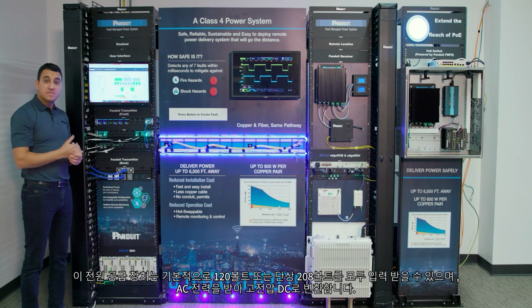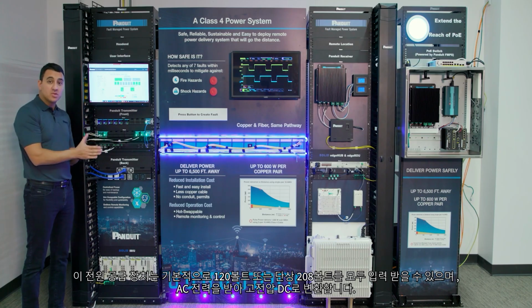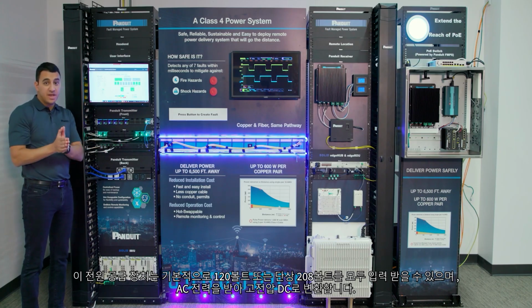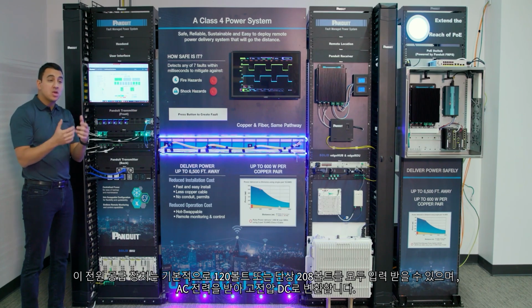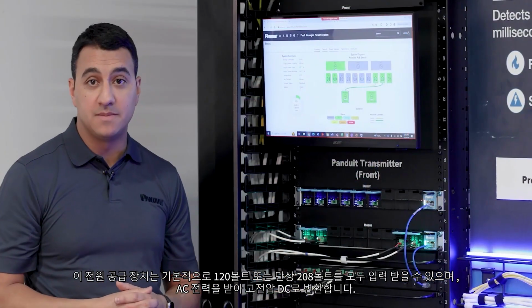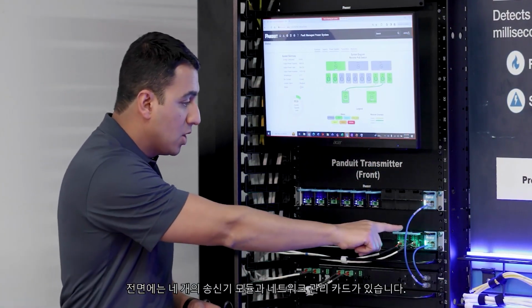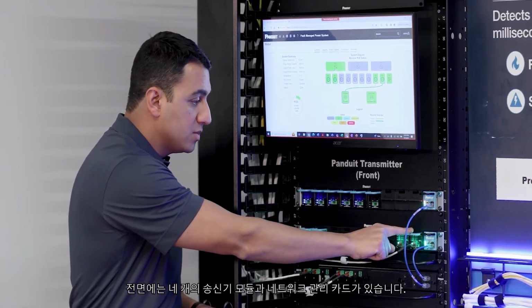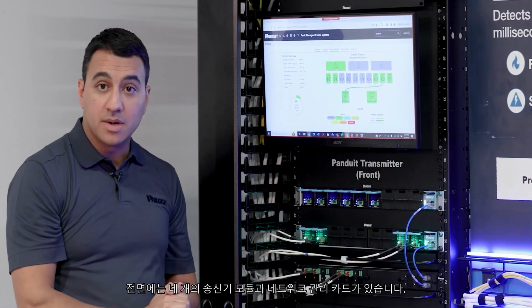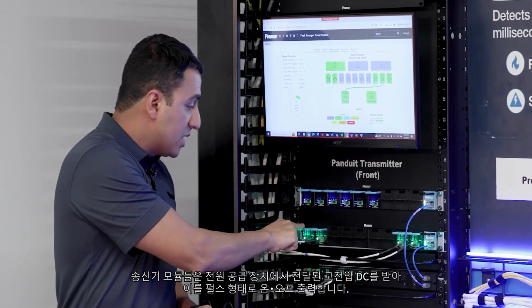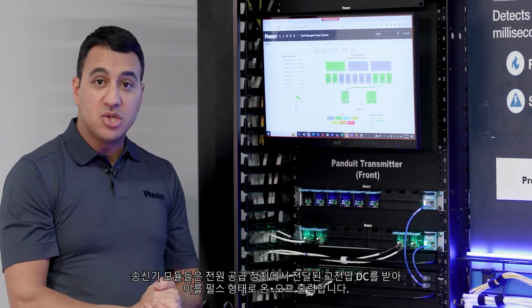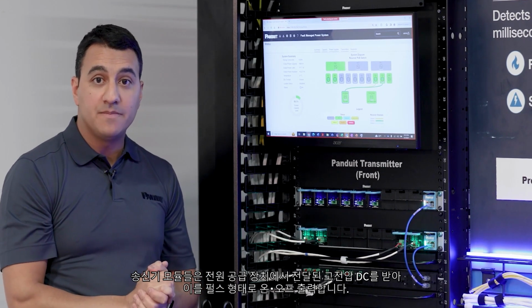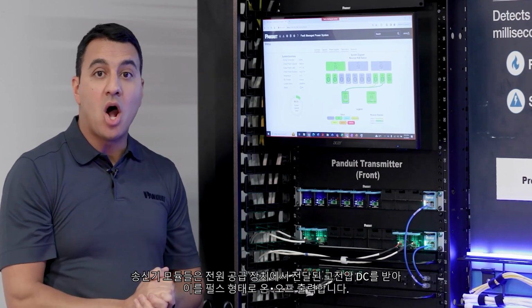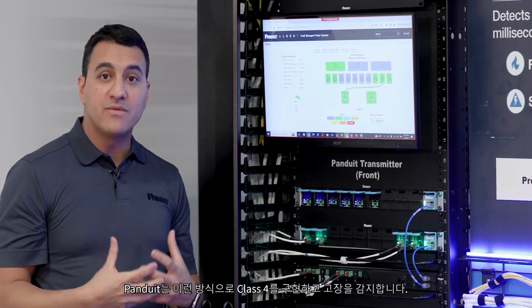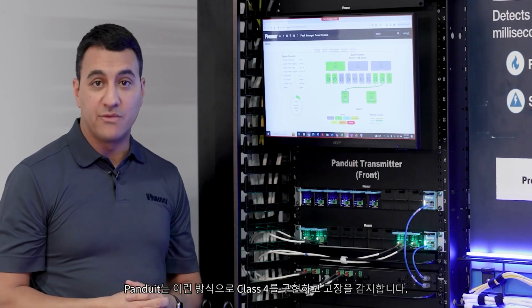That power supply unit can take anywhere from 120 volt or a single phase 208 volt. It takes that AC power and converts it to high voltage DC. In the front here, we have 4 transmitter modules and the network management card. The transmitter modules are taking that high voltage DC from the power supply unit and then pulsing it on and off. This is our way of doing class 4 and detecting for faults.